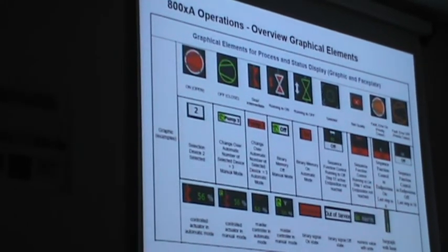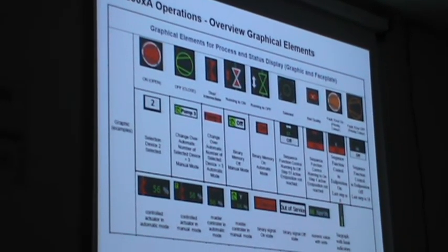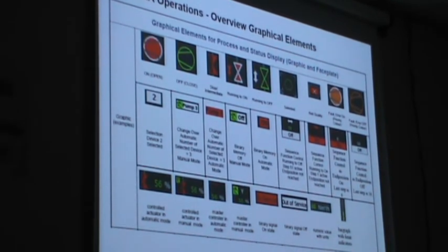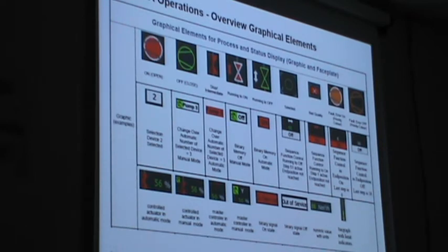When you use Profibus, you don't need to take more cables from the field. We use only 2 panels for all the field instruments like your transmitters and control valves. Here we have almost 800 transmitter signals connected with only these 2 panels. So all over the plant, there are no different marshalling panels other than this.